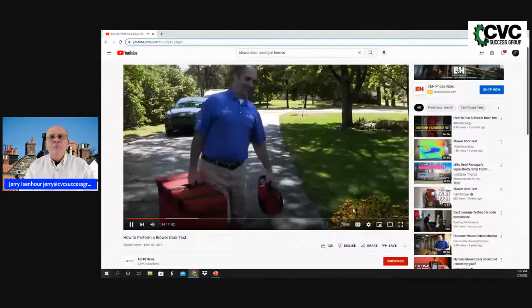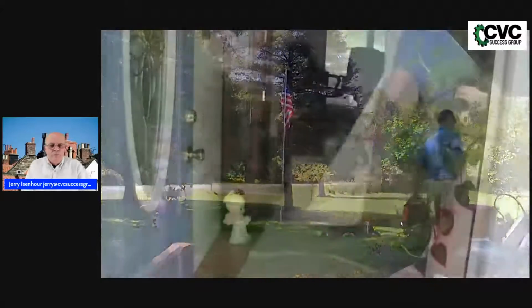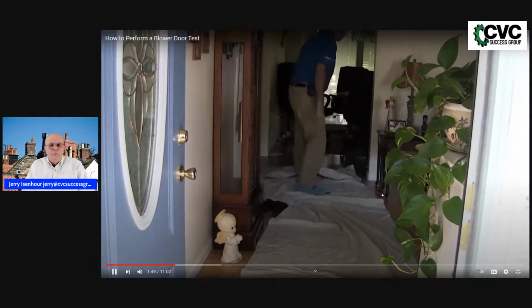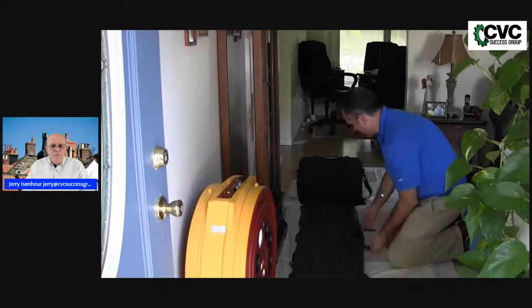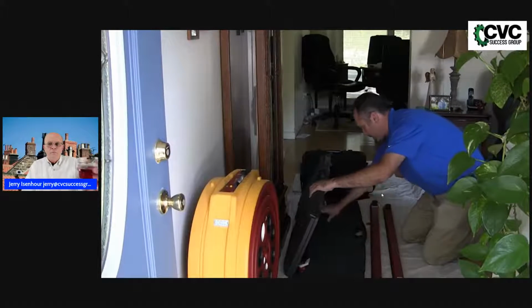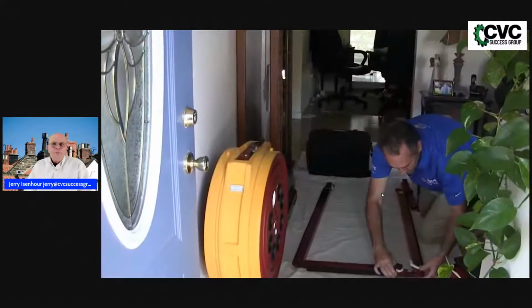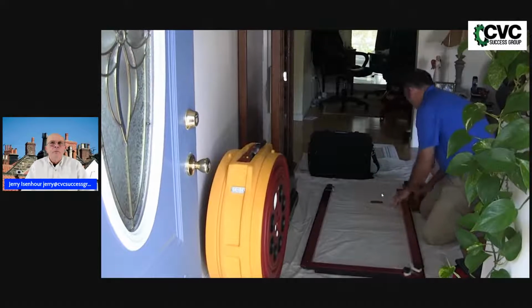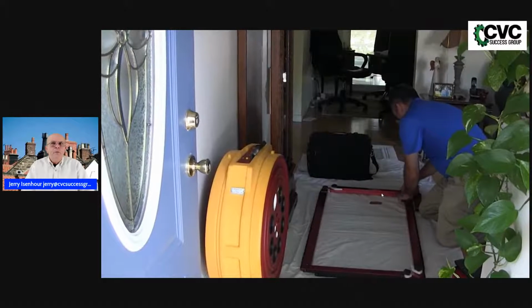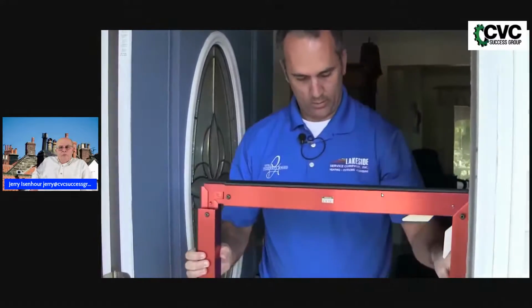For blower door testing, we follow the BPI, the Building Performance Institute, national standards or protocols, such as testing for any gas leaks in the house using a gas sniffer. We also put the house in its worst case conditions, which is for the CAZ zone, which is typically where the water heater and or furnace is located. Any of the natural venting appliances, like an 80% furnace or an 80% water heater. So we want to see if all the fans in the house run, like the bathroom fans and the stove fan, if it's going to make it so that that appliance can properly vent, can it properly exhaust. If it's going to backdraft, and if it's going to come into the house, or if it's going to spill, we call that spillage, then we have a way of testing for that, even before the blower door. So one, we know that the house is safe, and two, we know that the equipment is still going to operate effectively, even in its worst case conditions.